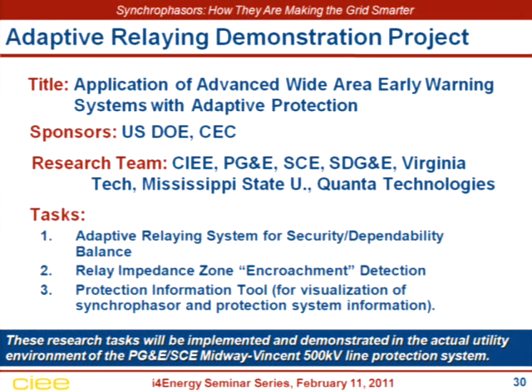Now, the project that we're doing is called Application of Advanced Wide Area Early Warning Systems with Adaptive Protection. But basically, we're going to be demonstrating three things. How to adapt the relaying system for security and dependability. That basically means how does it detect stressed systems and how does it supervise the relay characteristics so that it doesn't trip when it doesn't need to.